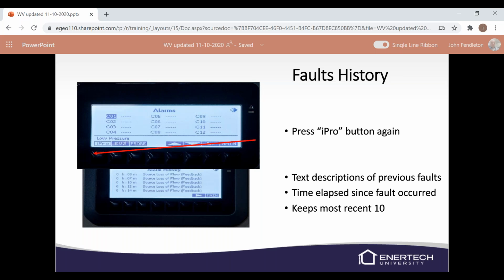So if you kill the high voltage power to the unit, and you turn it back on, it'll still hold those faults. If you look really close in that bottom picture, we had a low loss of flow feedback, 3 minutes ago, 7 minutes ago, 10 minutes ago, 12 minutes ago, and 14 minutes ago. So it'll kind of show you how long ago those happened and what faults those were.